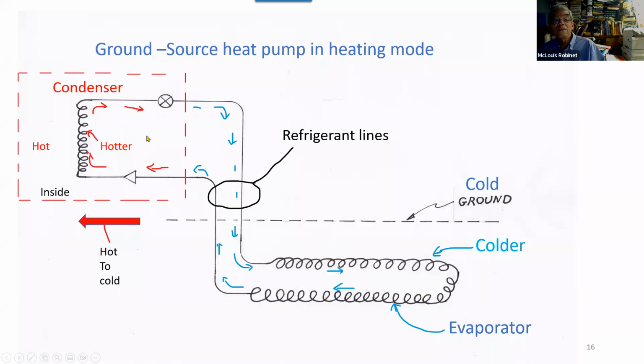There was a company in Florida about 20 years ago that actually made a system like this. It's very efficient because you have copper tubing that conducts heat well. But the problem is copper deteriorates, and you've got a lot of expensive refrigerant here. If you spring a leak, you contaminate the surroundings. So this is a bad idea, but it works well.